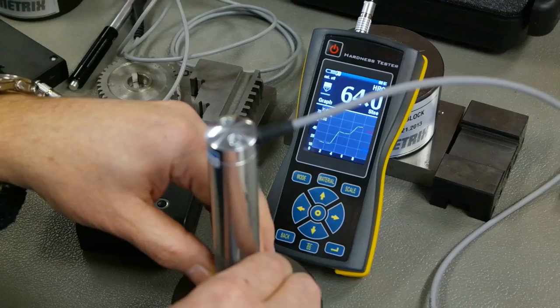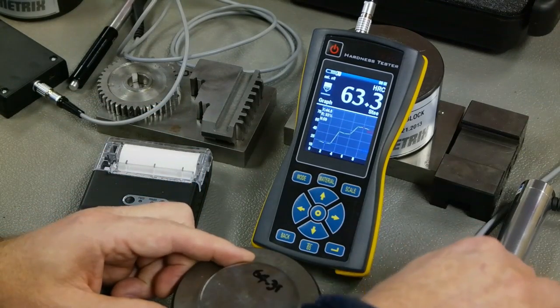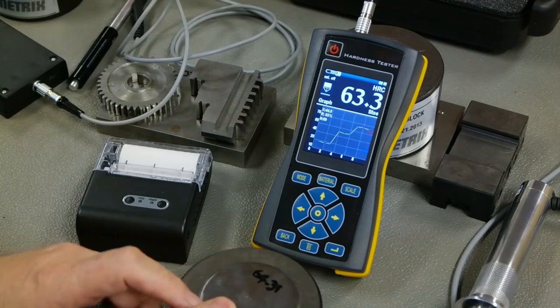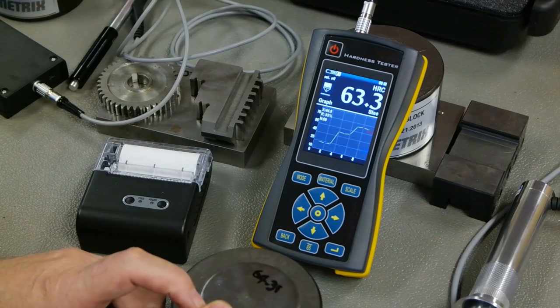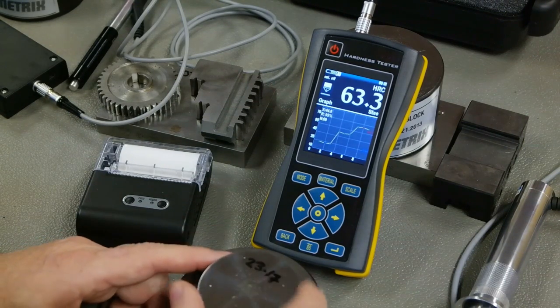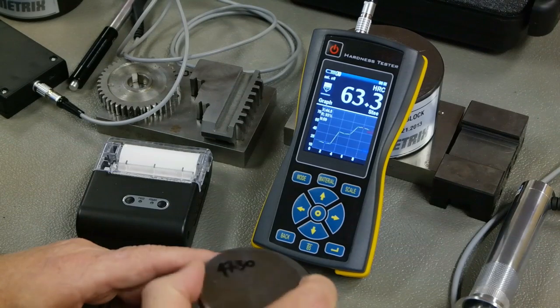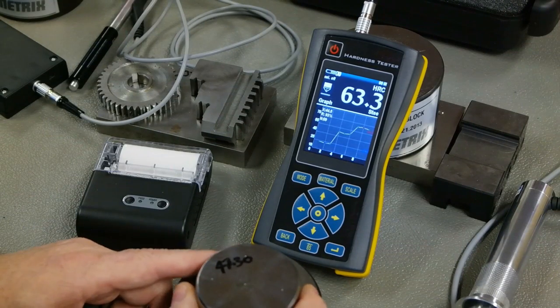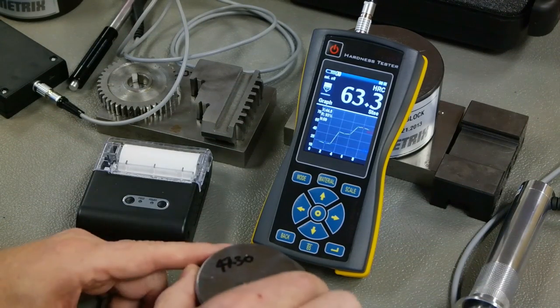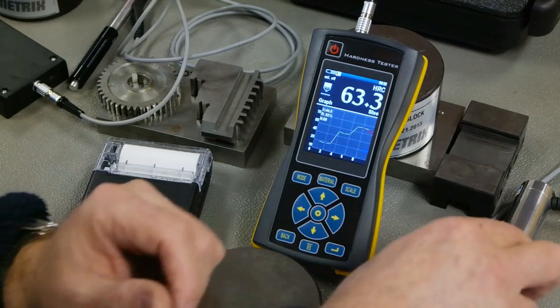63.7, 64, 63.3. So you can see super accurate, bearing in mind that this has a 0.5 tolerance on its hardness across the surface. This had a 1 tolerance, and this had a 1 tolerance as well, and we are well within those tolerance bands based on these traceable test blocks.